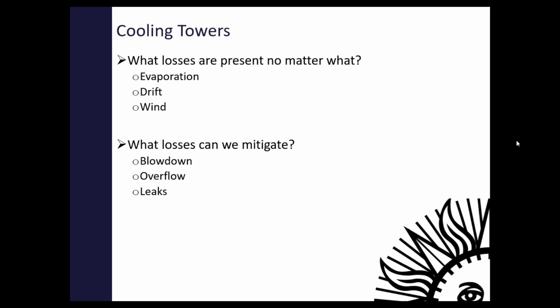So what losses can't we deal with? Evaporation, of course. Water has to evaporate to remove the energy. Drift is always present, and wind, you can't control the wind, but you can put wind screens on your cooling tower to mitigate wind losses if you are in a very windy climate. What other losses can we mitigate though? Blowdown, overflow, and leaks. Blowdown especially.